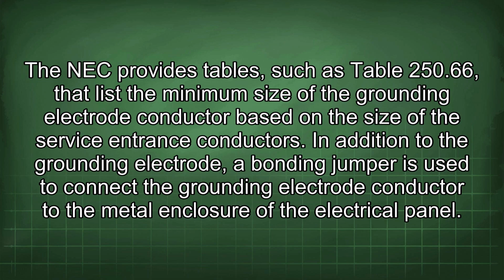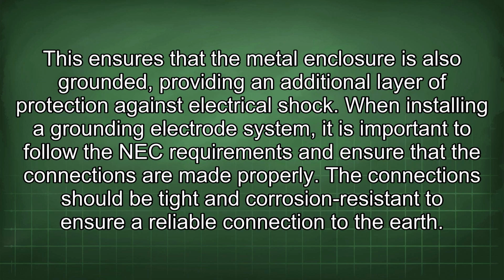In addition to the grounding electrode, a bonding jumper is used to connect the grounding electrode conductor to the metal enclosure of the electrical panel. This ensures that the metal enclosure is also grounded, providing an additional layer of protection against electrical shock. When installing a grounding electrode system, it is important to follow the NEC requirements and ensure that the connections are made properly. The connection should be tight and corrosion resistant to ensure a reliable connection to the earth.